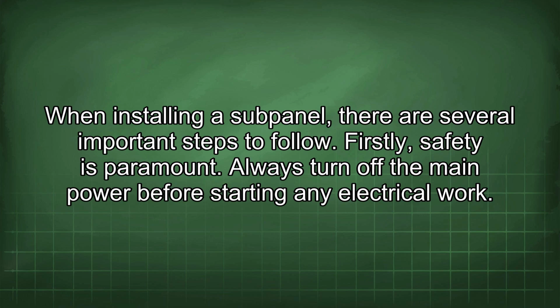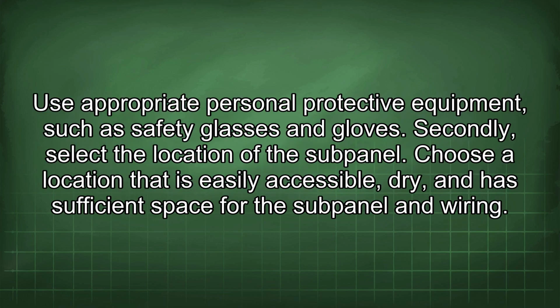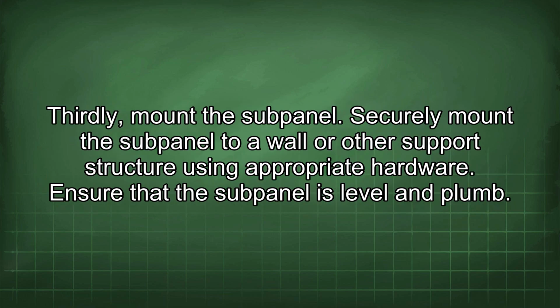When installing a sub-panel, there are several important steps to follow. Firstly, safety is paramount. Always turn off the main power before starting any electrical work. Use appropriate personal protective equipment, such as safety glasses and gloves. Secondly, select the location of the sub-panel. Choose a location that is easily accessible, dry, and has sufficient space for the sub-panel and wiring. Thirdly, mount the sub-panel. Securely mount the sub-panel to a wall or other support structure using appropriate hardware. Ensure that the sub-panel is level and plumb.